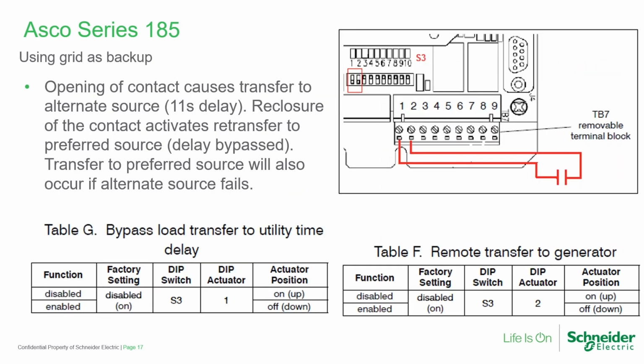If you remember our previous slide when we were using the grid as a backup, the alternate source can be the XW Pro system because external relay is normally open, meaning the XW Pro system is the normal mode of operation. The aux port would trigger active high once the low battery condition is met to close the external relay. This will cause transfer to the grid with zero delay because if you look at the chart there, we've got dip switch S3 position 1 enabled. So what that does is it bypasses the utility time delay to zero.